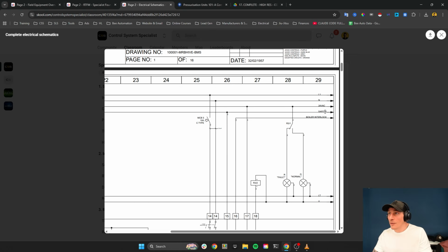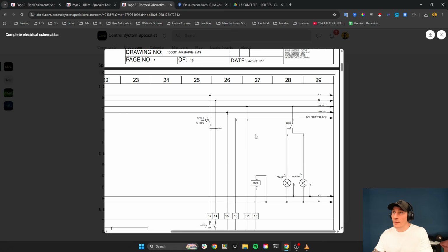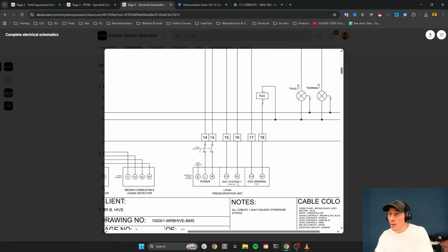Then what we've got off this safety circuit, which is ultimately a 24 volts AC supply circuit, if various things upstream are healthy, so relay 1 is energized and that's healthy, that sends power down this safety circuit down here, which is 24 volts AC as I mentioned, and then that comes down here into the common of the digital output relay of the system.